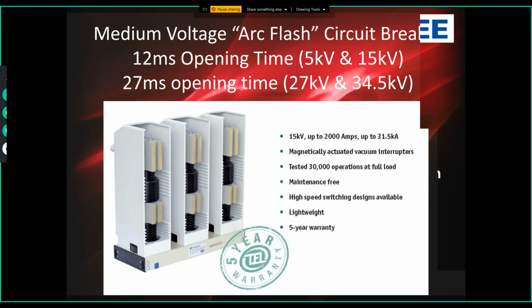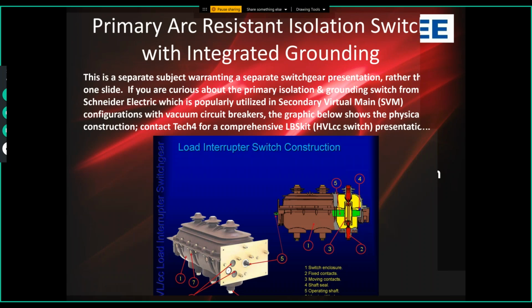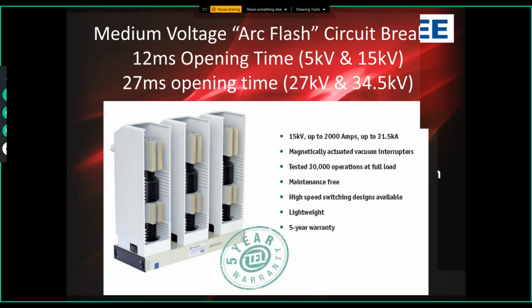So even though the switch is load break rated, it's electrically interlocked, so the breaker here is always breaking the load. That isolation switch here could be equipped with a shunt trip, Ramesh, but it is not fault current break rated. It's load break rated, but not fault current rated. So you can't connect a relay up under a 50-51 relay and shunt trip the switch under fault current conditions. That's not possible. It's not rated for that. The overcurrent protective relay must open the circuit breaker itself.